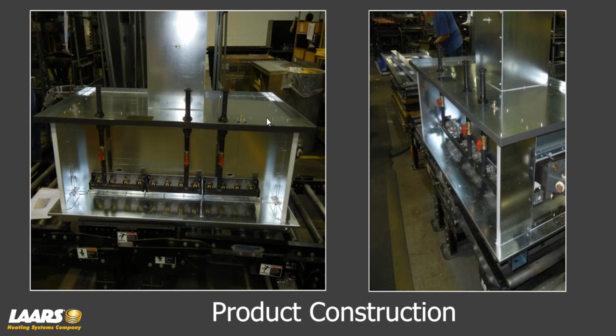Now, to measure combustion air, we'll have two pressure switches. We do not want to go into ignition if your combustion air fan is not running or working. So again, we're blowing combustion air down into a chamber, and we have a barb, and I'm showing the side view here. That barb will have a vinyl tube that goes off to an air pressure switch. That air pressure switch is normally open. So air pressure closes the switch, and then we'll go into the ignition sequence.